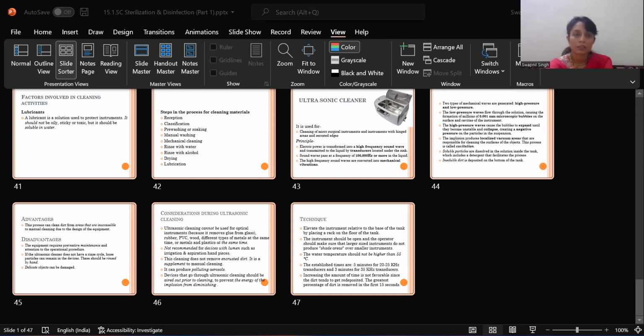Principles of sterilization. Now, instruments should be thoroughly cleaned before sterilization. The sterilization agent must be in contact with every surface of the item for a specific period of time and at a specific temperature. All sterilizing equipment must be regularly serviced and maintained. Appropriate tests must be applied to check temperature, humidity, and pressure along with the gas content. The manufacturer's instructions should be strictly adhered to for operation and maintenance.